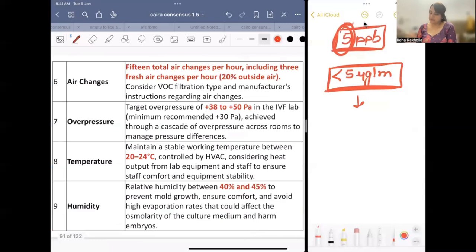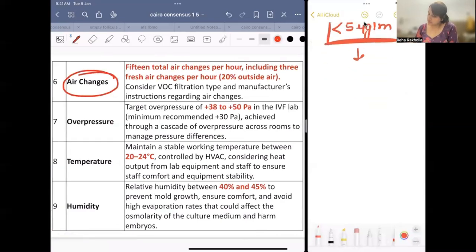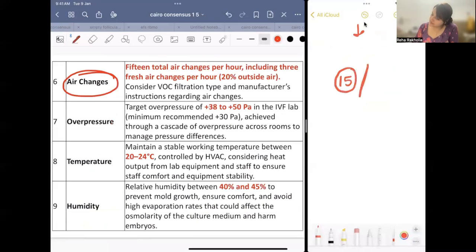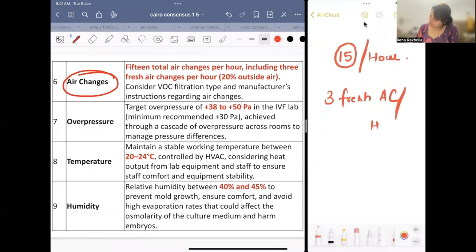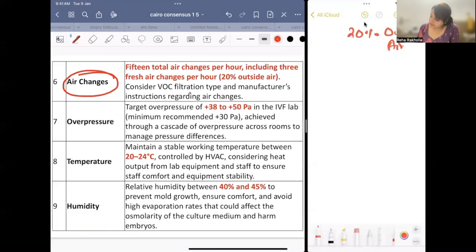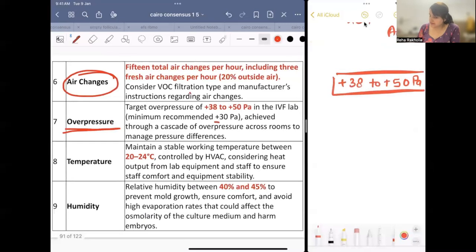Now we'll talk about air changes. Air changes should be 15 total air changes per hour, including three fresh air changes per hour, which means 20% outside air. Consider the VOC filtration type and manufacturer instructions regarding air changes. Overpressure: we should maintain a positive pressure in the laboratory. Optimal should be plus 38 to plus 50 Pascal in the IVF lab. The minimum recommendation is plus 30 Pascal across the room.